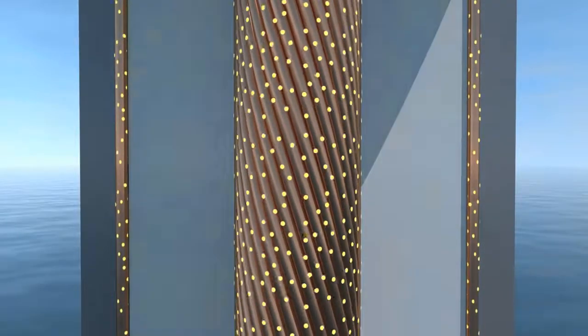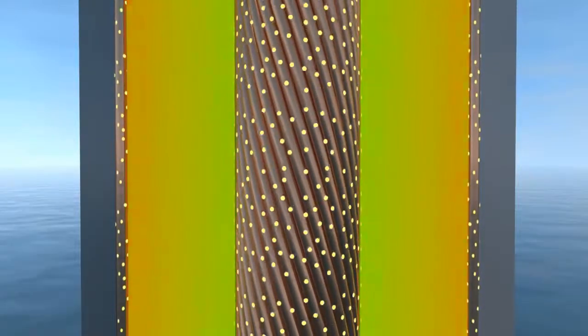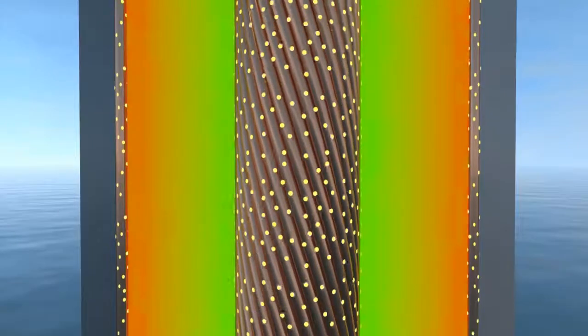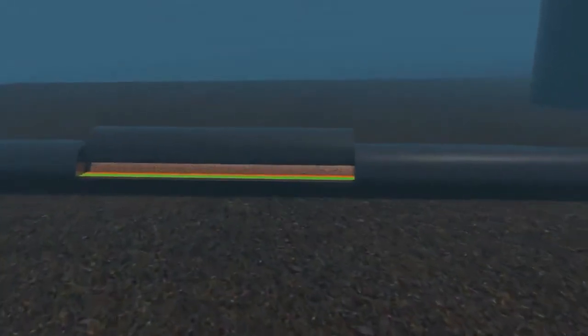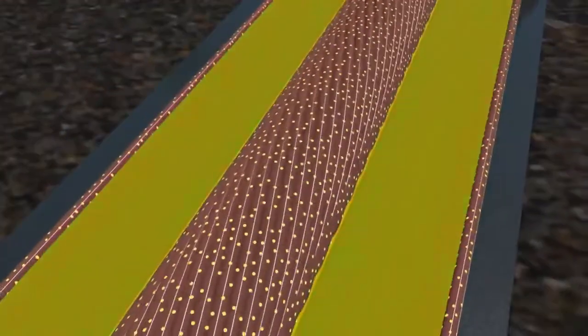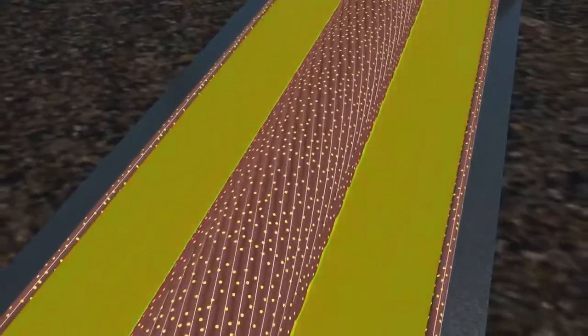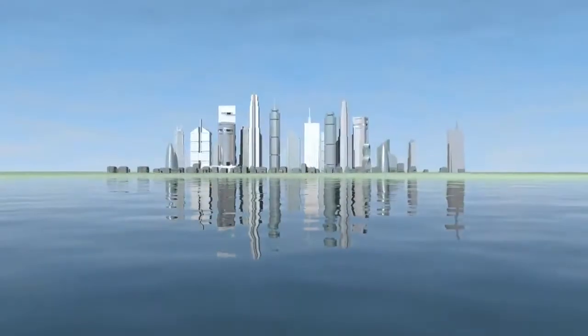The problem is that unlike high-voltage power lines on land, the sea cables' conductors are very close to each other. As a result of physical effects, the currents continuously charge and discharge the isolator like a battery. The longer the cable, the more electricity is needed for this continuous charging and discharging. For lengths of more than about 70 kilometers, the charging current blocks up the sea cable, and no more wind power can be transported to land.